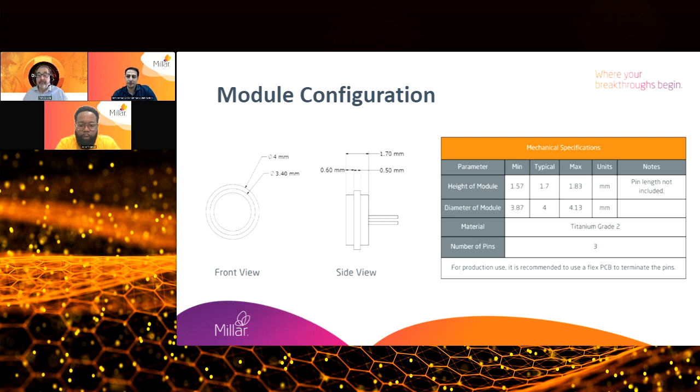Valor? I think when we were designing the TiSense sensor, mitigating risk was at the foremost of our thinking. The titanium grade 2 has been used for decades in medical applications and has been proven safe from a biocompatibility standpoint. The vast data associated with this material led us to choose it to limit the risk associated with device developers integrating it into their devices.